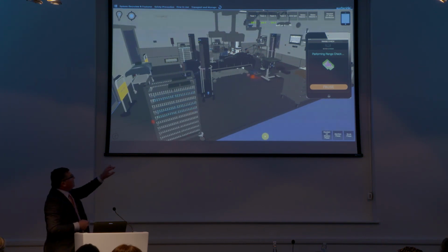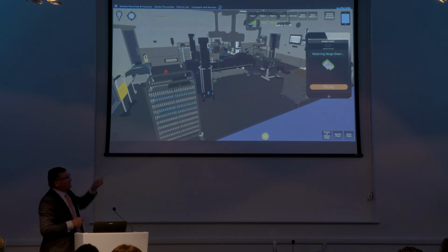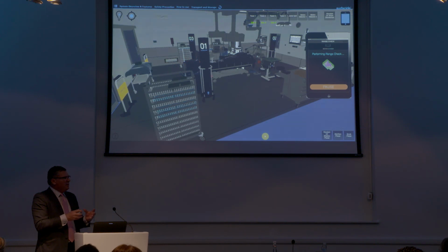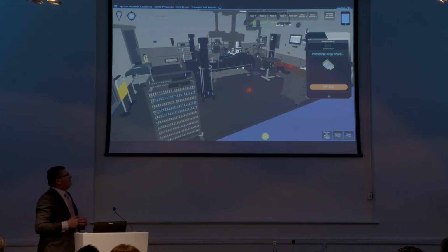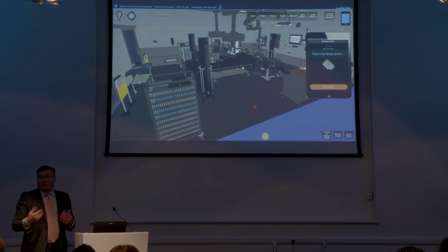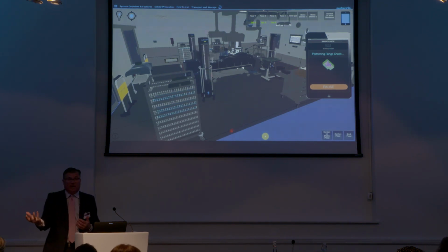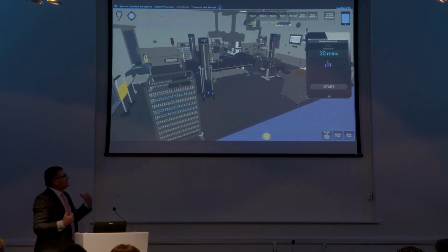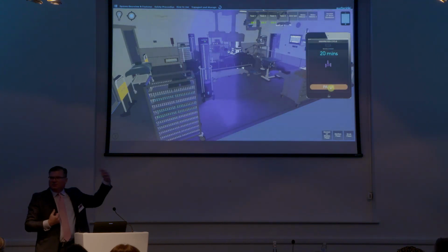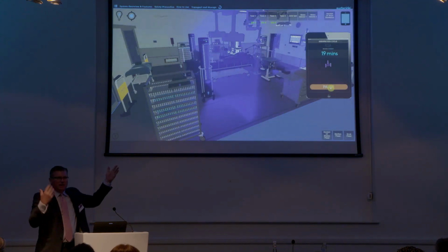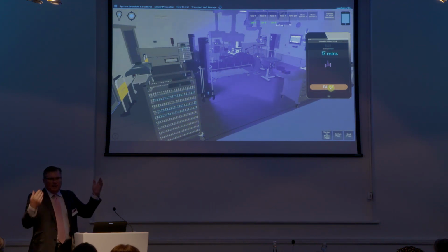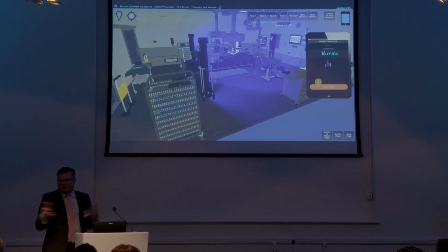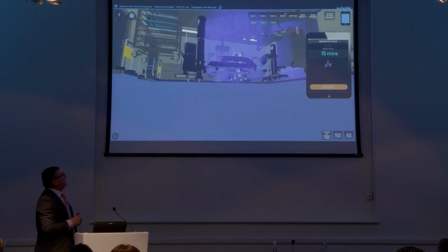It will then do a near field scan as well to identify those objects that are nearest to each tower so that the tower nearest is prioritizing the objects nearest to it. The algorithm will then run and calculate the cycle time. A lot of our customers will do this during the first 10, 15 days of operation, and then for given room spaces, they'll just run that cycle time for consecutive cycles just to save the few minutes of laser mapping.